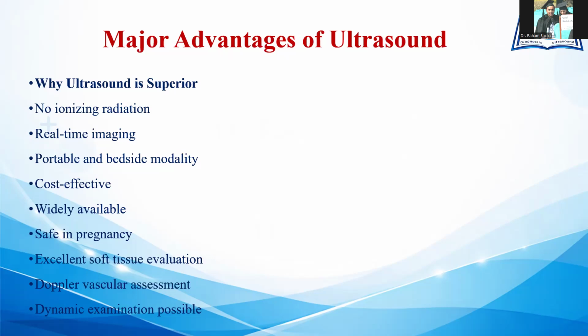Its soft tissue resolution is excellent, right? While using a high frequency transducer, we will have high spatial resolution, particularly axial resolution. For example, if we are using a high frequency of 14 megahertz, then the axial resolution of ultrasound becomes better than MRI. I'm not talking about contrast resolution, only the axial resolution.